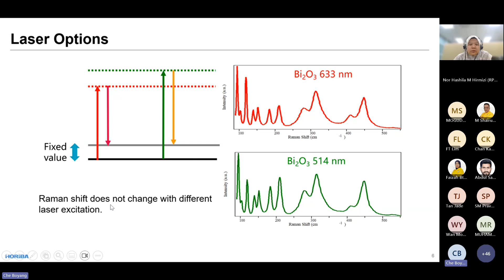Here we compare the same sample tested by two different lasers, 633 and 514, so a red laser and a green laser. But if you check the final result, the Raman spectrum is exactly the same. Your peaks appear at the same Raman shift. This shows you the Raman shift result does not change with different laser excitation.